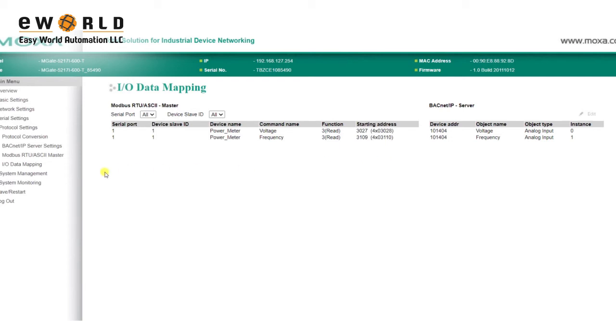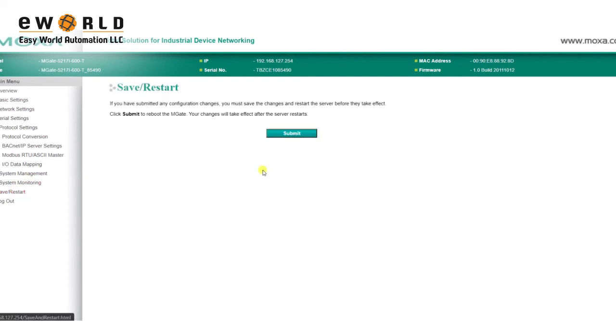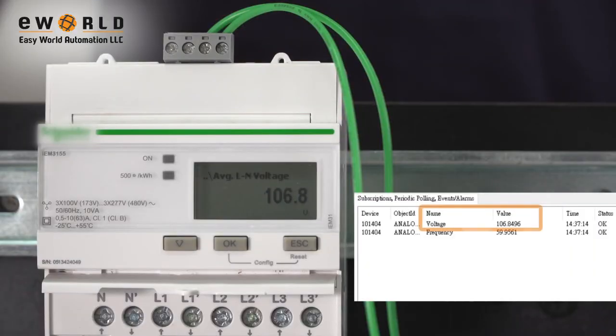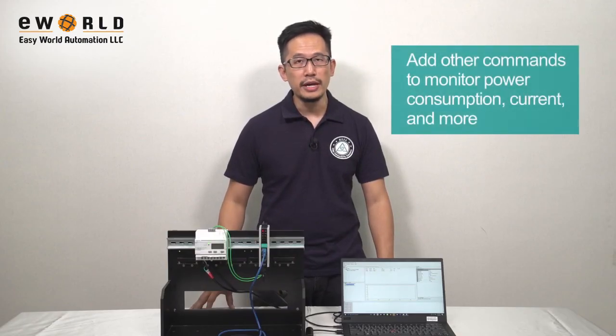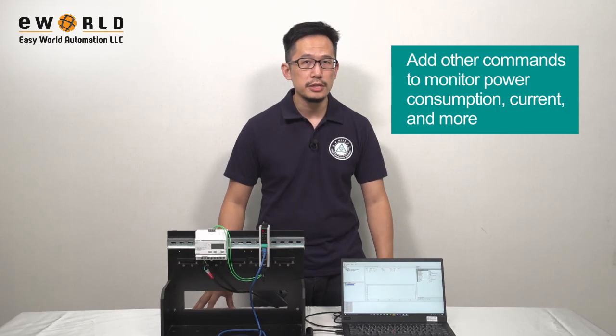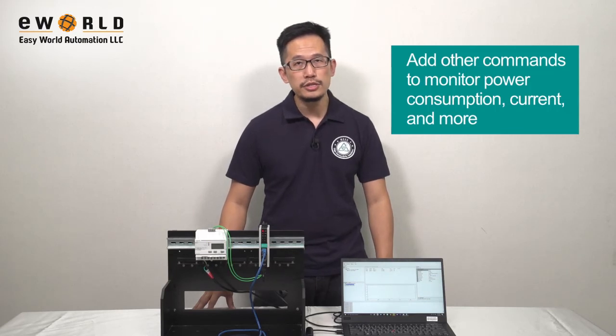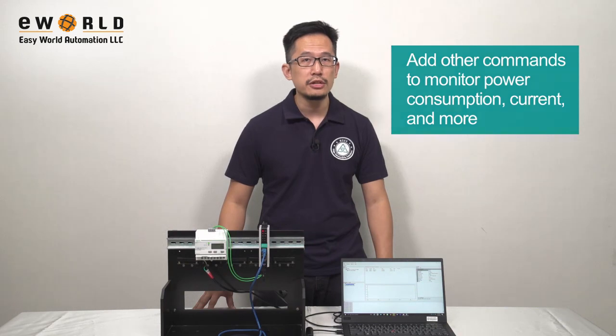After going to Save Restart and clicking Submit to apply our changes, we're done. Now, in our BACnet IP client, we can monitor our power meter's voltage and frequency data. You can follow these steps to add other commands so you can monitor power consumption, current, and more, giving you the data you need to optimize your energy usage. Thanks for watching, and see you next time.